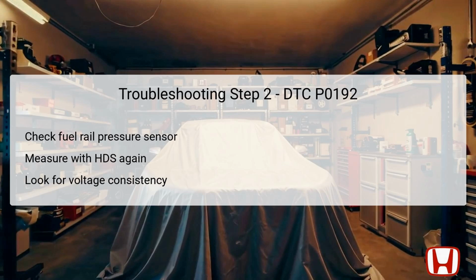These measurements will help in determining whether the issue lies with the sensor itself or within the wiring that powers it. If the voltage reading is above the threshold, then it prompts the next step of checking lines connecting to the PCM for further diagnostics. Each of these steps is foundational in isolating the failure area accurately.